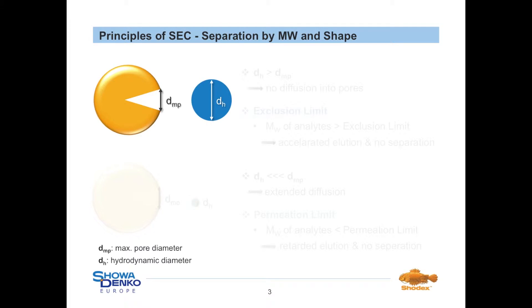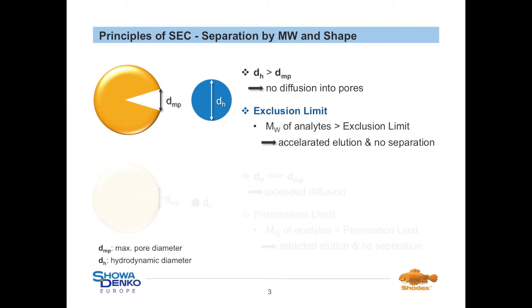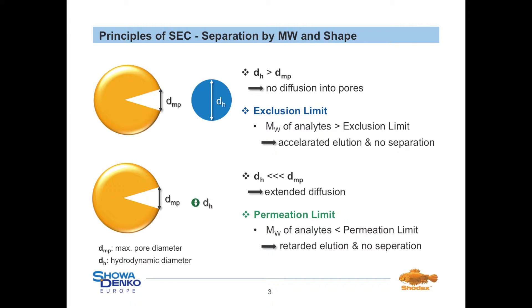When size exclusion columns have to be chosen for a certain application, several facts have to be considered. In general, for every size exclusion column the pore sizes and also the exclusion limit are given as typical characteristics. Under aqueous conditions the exclusion limit is determined by different standards like pullulan, which is an unbranched polysaccharide, and proteins. In case the compound has a bigger hydrodynamic diameter than the maximum pore size diameter, no diffusion into the pores is possible. Therefore no separation above this limit is possible. The same effect occurs when the compound has a significantly smaller hydrodynamic diameter than the smallest pore size available — in this case the compound will retain on the column much longer and ends up in a retarded elution. This limit is called the permeation limit.